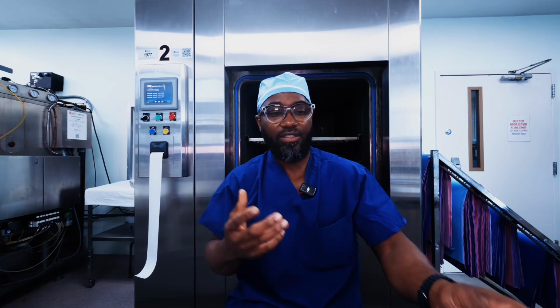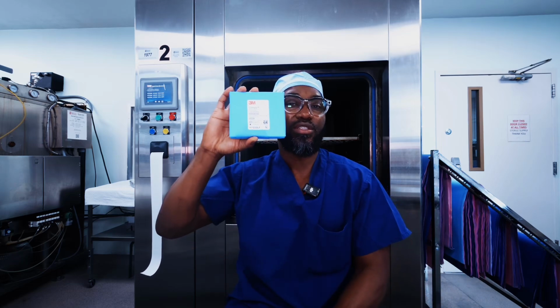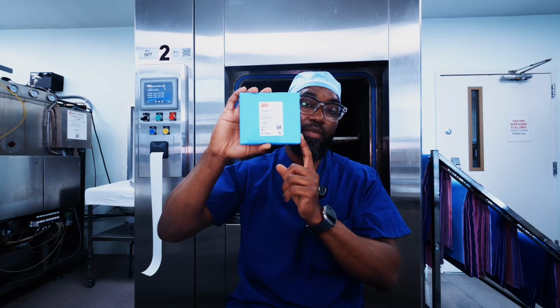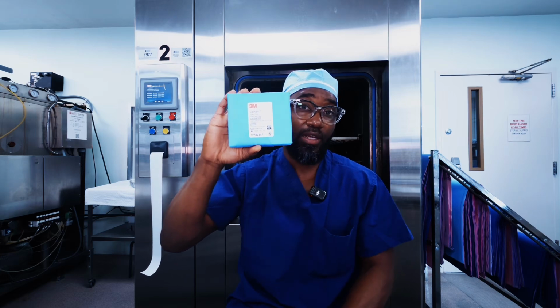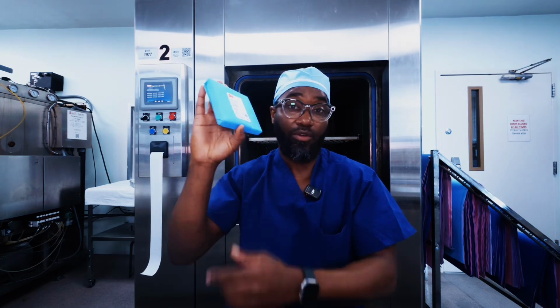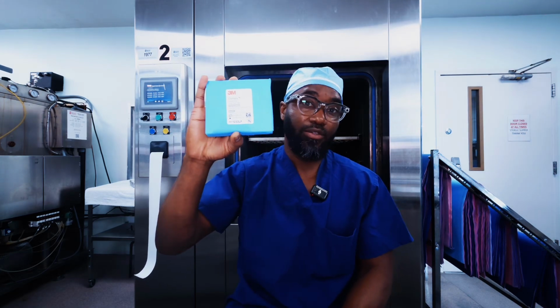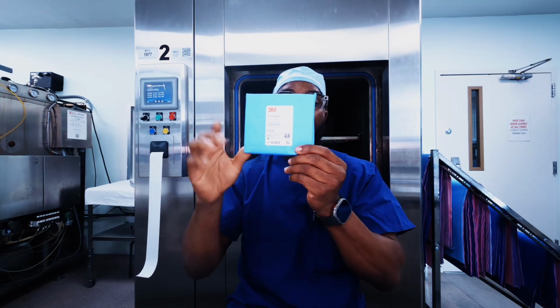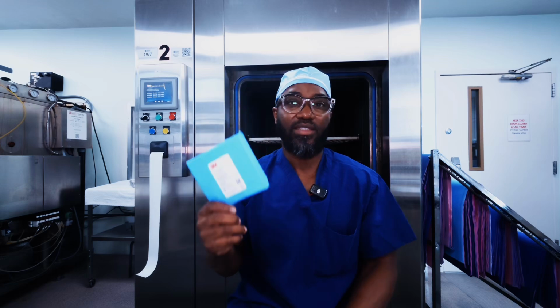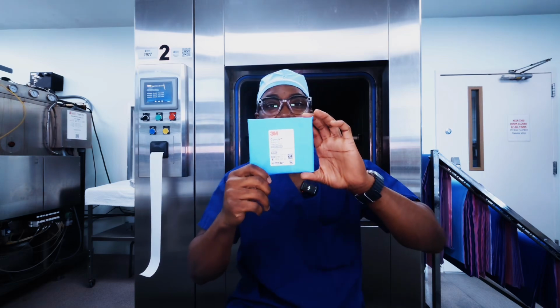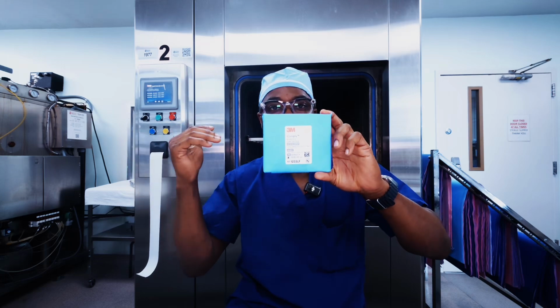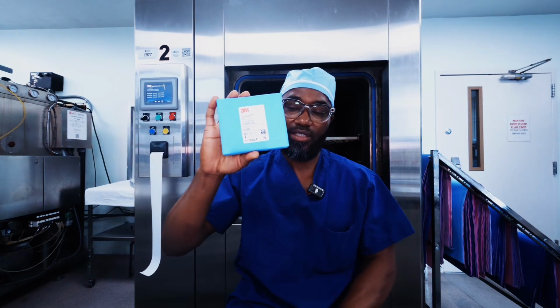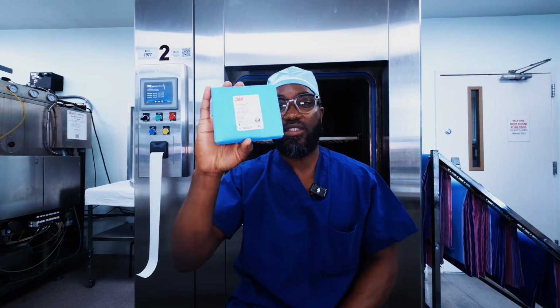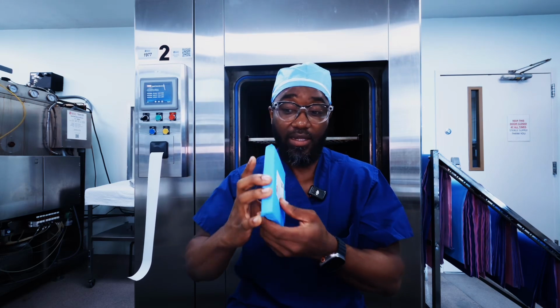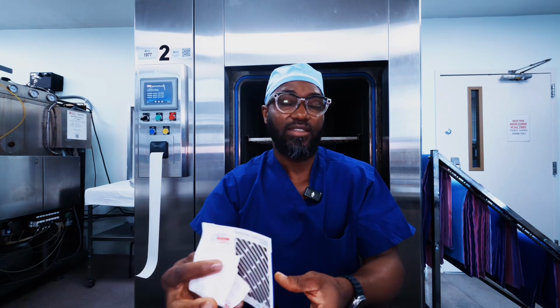In order to find out how it's done, we use a type 2 chemical indicator, which is the Bowie-Dick air removal test. And remember, this might not look the same as what you might use at your facility. This Bowie-Dick air removal test is manufactured by 3M. This test is run first thing in the morning, and it tests this chamber to make sure it is taking all of the air out of the sterilizer before the sterilization process starts. After this process is completed, we inspect the indicator in here to make sure it passes.